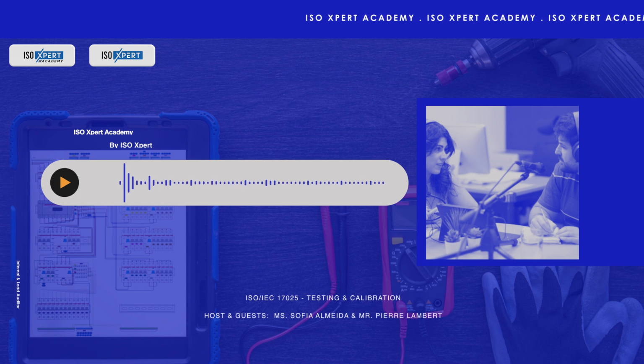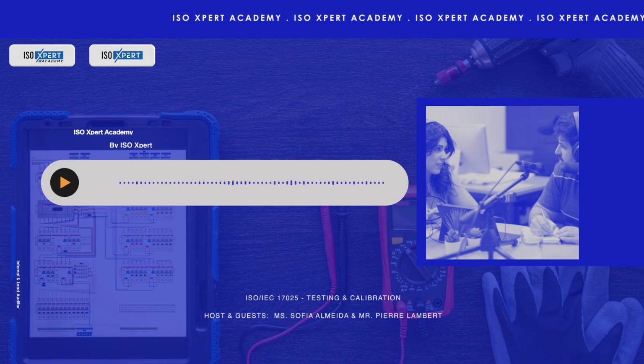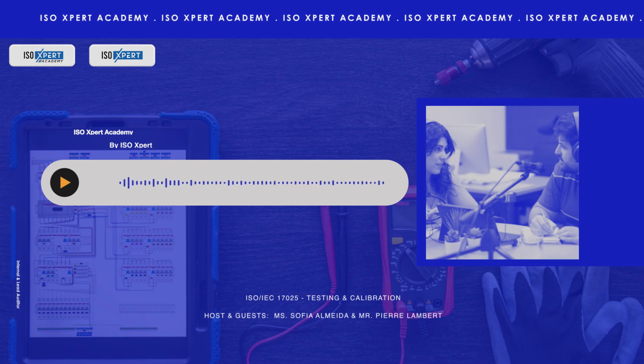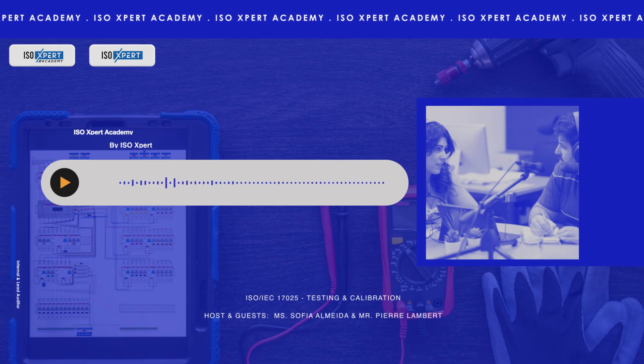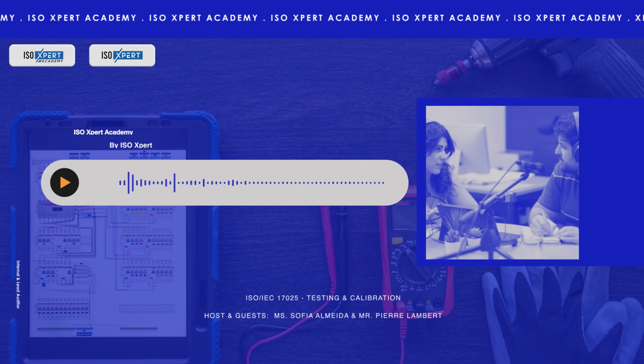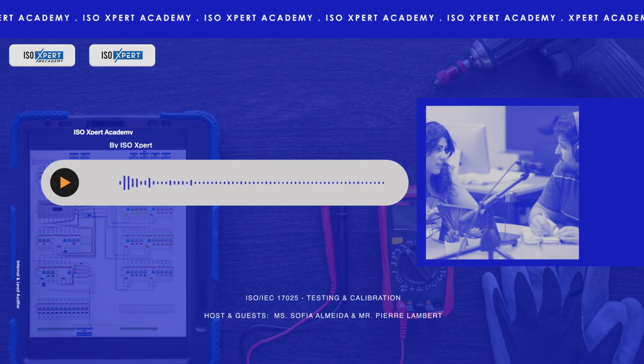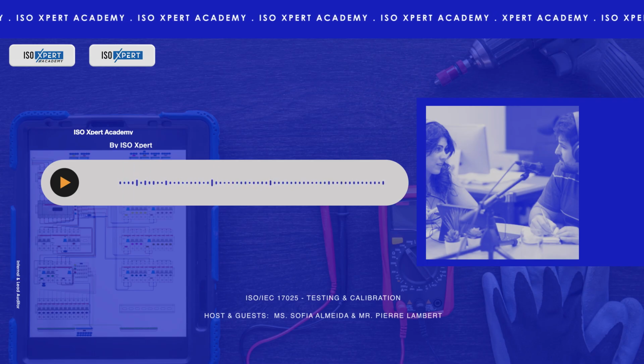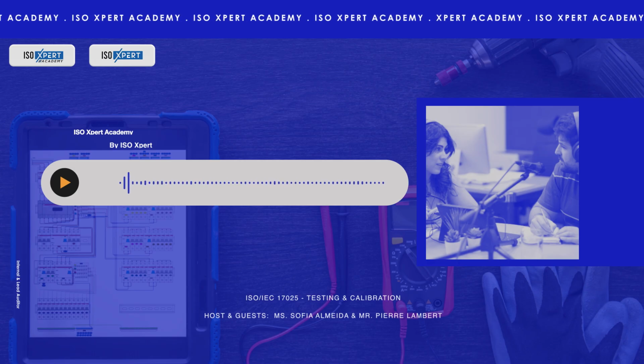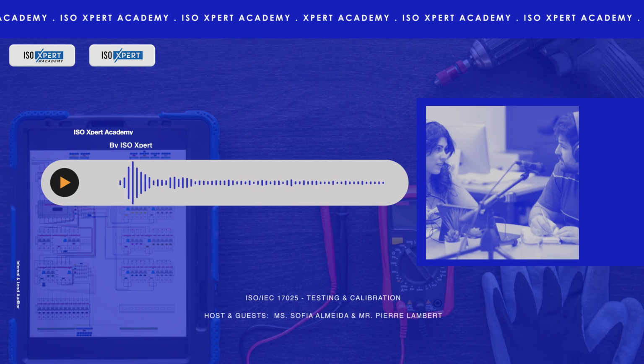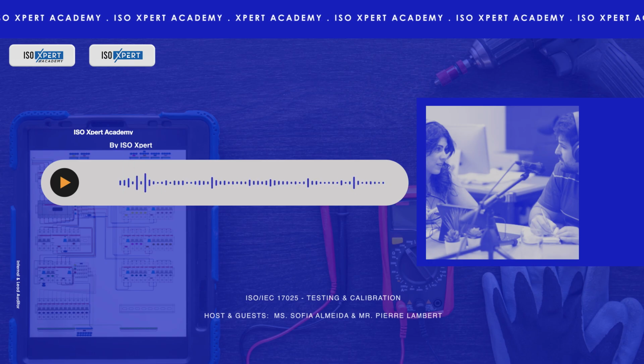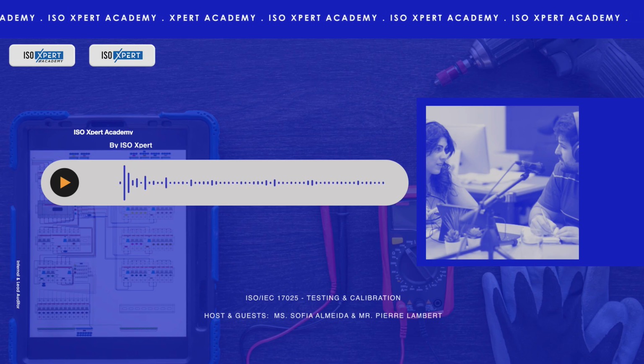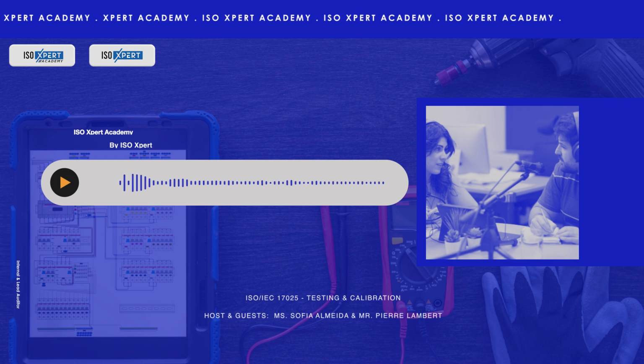Following the chain back and back until it connects to a national standard held by, say, NIST in the US, or NPL in the UK, or an equivalent National Metrology Institute. Or maybe to a recognized certified reference material producer. And they confirm the lab uses accredited calibration services for this, ensuring the competence of those providing the calibration. Wow. So it's like a scientifically precise family tree for every single measurement. That's what allows results from different labs, different countries, even different decades to be reliably compared because they all trace back to the same ultimate reference point.